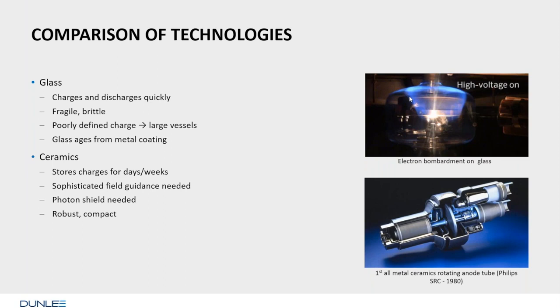And also, last but not least, the glass is subject to coating. Typically, it is around the anode and the cathode. So it's coated with tungsten from the anode and also from the cathode, evaporating cathode.